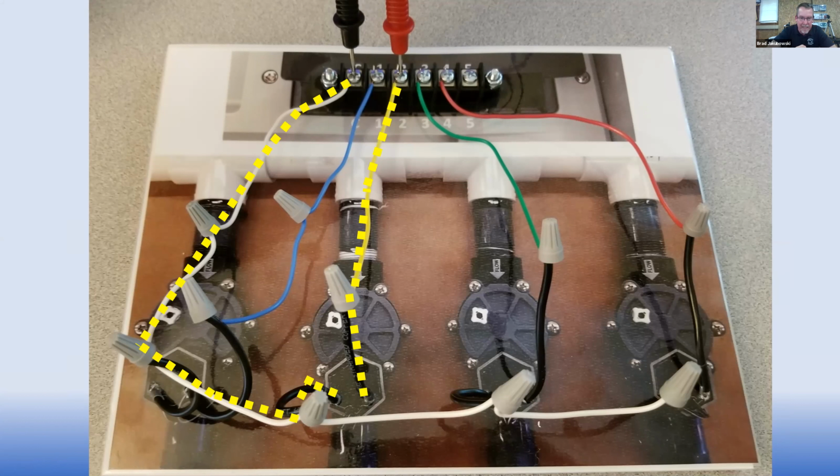And remember, that's key. Knowing your order of operation becomes very critical when you're troubleshooting. So whether it's electrical like this, or if you're teaching them how the operation of a valve and head sprinkler works for golf, the order of operation becomes critical. So one of the first things that we would test, power in, power out.